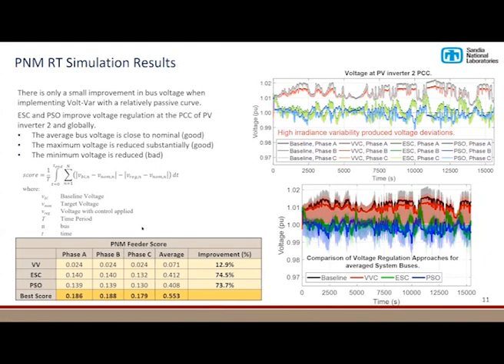And so we wanted to come up with some sort of metric or scoring for these different simulations, and we came up with this. So we're just integrating over time a scoring for a baseline test minus the voltage regulation case. And so if you, on the baseline case, moved from that point down toward nominal, you would score better. And so volt-var had an improvement in terms of this metric of about 13%. And the extremum seeking control and particle swarm optimization did much better, like a 75% improvement. So not bad.